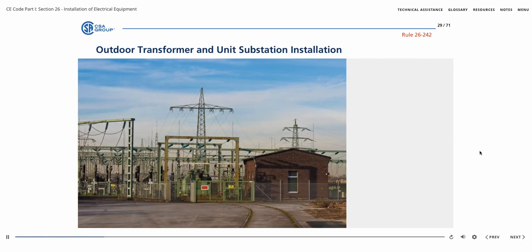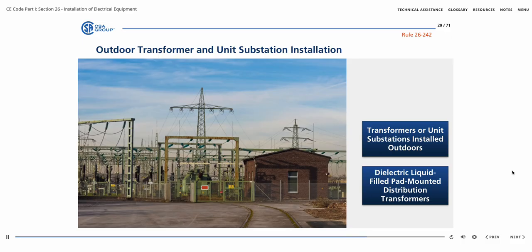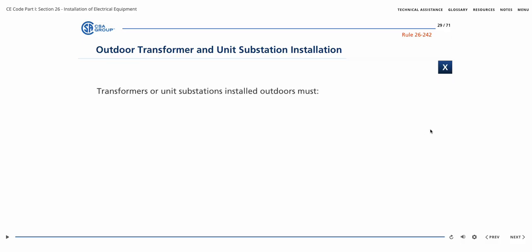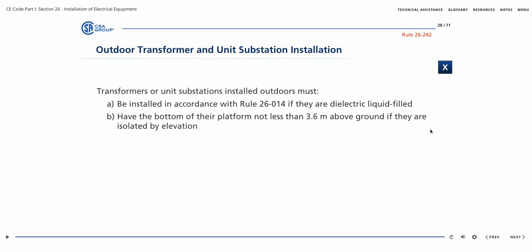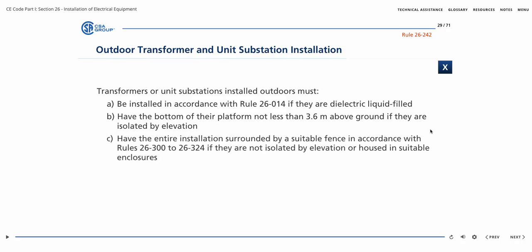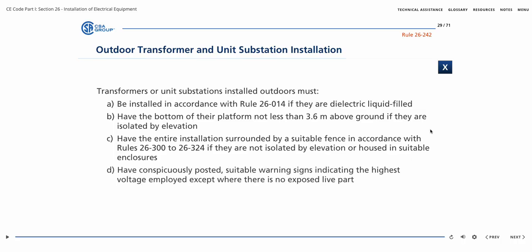Installing transformers and unit substations outdoors must be completed carefully. Rule 26-242, Subrules 1 and 2, point out the safety standards for installation. Transformers or unit substations, including their conductors, cables, and control and protective equipment, installed outdoors are required by Subrule 1 to: A. Be installed in accordance with Rule 26-014 if they are dielectric liquid-filled. B. Have the bottom of their platform not less than 3.6 meters above ground if they are isolated by elevation. C. Have the entire installation surrounded by a suitable fence in accordance with Rules 26-300 to 26-324 if they are not isolated by elevation or housed in suitable enclosures, and D. Have conspicuously posted suitable warning signs indicating the highest voltage employed, except where there are no exposed live parts.